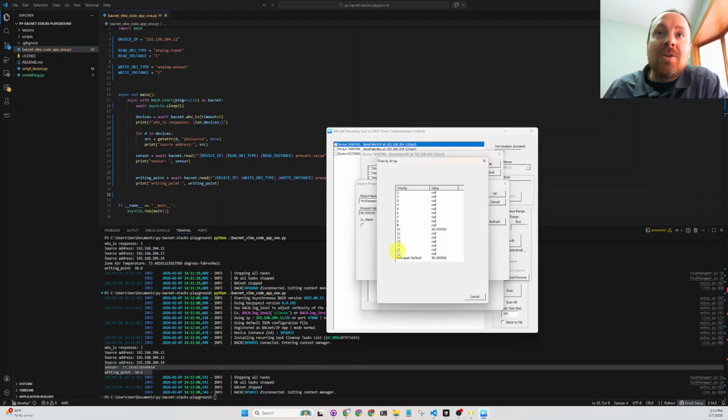If automation writes here, the building operator can still override it, because anything above means the highest priority, which is the lowest number, which is confusing. So like my value of 88 at priority 10, if the building operator came in, they can override me because they're a higher priority. And let's say the building automation is writing here, I would override the building automation with Python, and then the building operator can override me at priority 8. That's typically how people do things.